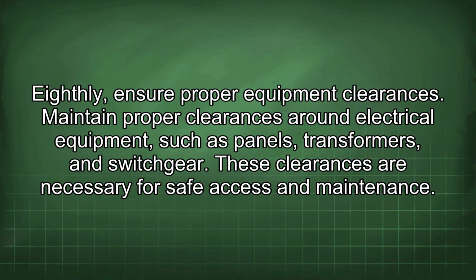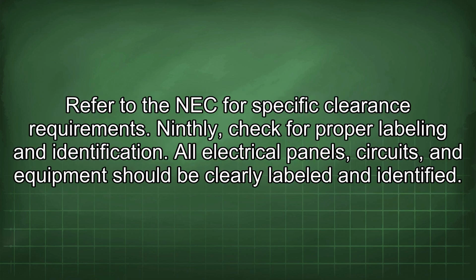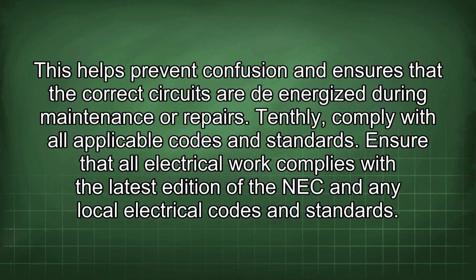Eighthly, ensure proper equipment clearances. Maintain proper clearances around electrical equipment such as panels, transformers, and switchgear. These clearances are necessary for safe access and maintenance. Refer to the NEC for specific clearance requirements. Ninthly, check for proper labeling and identification. All electrical panels, circuits, and equipment should be clearly labeled and identified. This helps prevent confusion and ensures that the correct circuits are de-energized during maintenance or repairs.